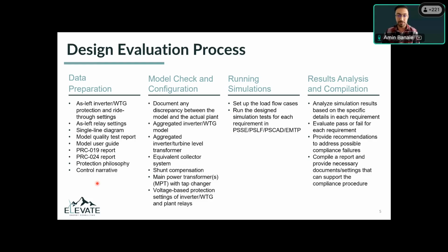The other piece is an accurate and working model. That can be either an EMT model or a phasor-based or RMS model. And PRC-019 can be evaluated in these two types of software. And the final piece, I would say, is the inverter manual that has the PQ curve of the inverters and the capability. That's also needed because PRC-019 has certain requirements, especially R2.2 and R2.3, that talk about whether reactive power is within the hardware limits of the inverter. So that information is also needed.